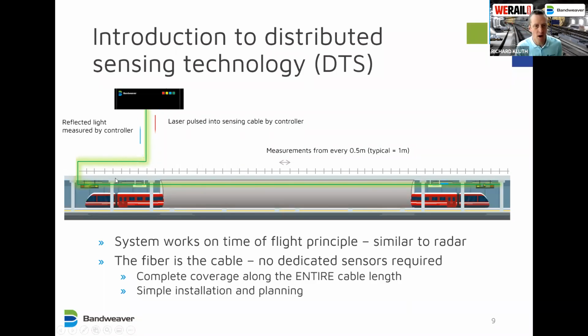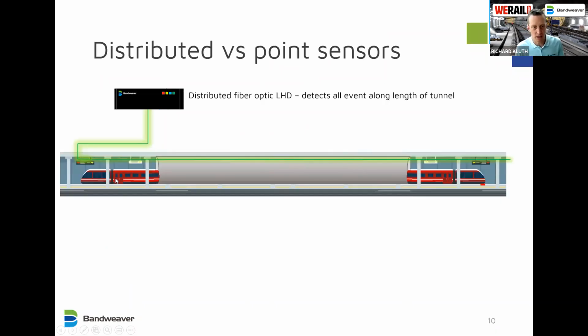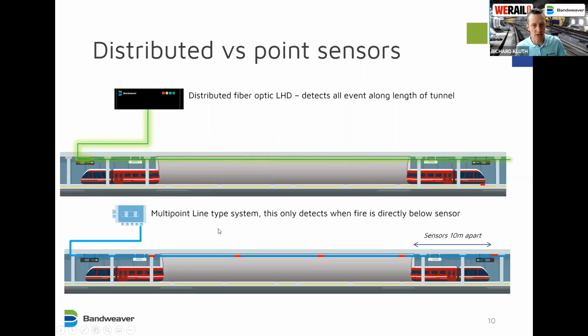And I'll just highlight the distributed nature here with an example comparison versus a conventional point sensor system. So if we imagine we have a fire at this point in the tunnel, the cable would sense the heat directly above it, and so you'd have a very fast reaction time. Again here, another small fire, you would have it directly above, and wherever you are, you get the picture. Wherever it moves, you would get it straight away.